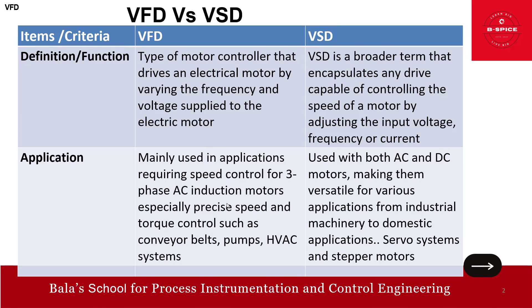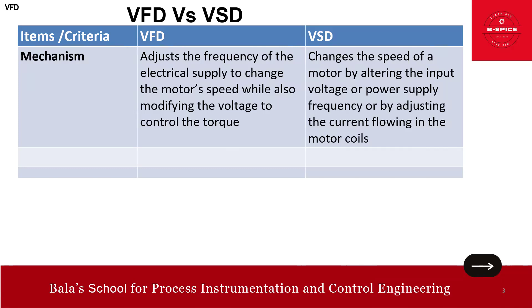In terms of application, VFDs are mainly used in applications requiring speed control for three-phase AC induction motors, especially where precise speed and torque control is needed — such as conveyors, pumps, and HVAC systems. VSDs, on the other hand, are used for both AC and DC motors, making them versatile for various applications from industrial machinery to domestic applications like servo systems and stepper motors.